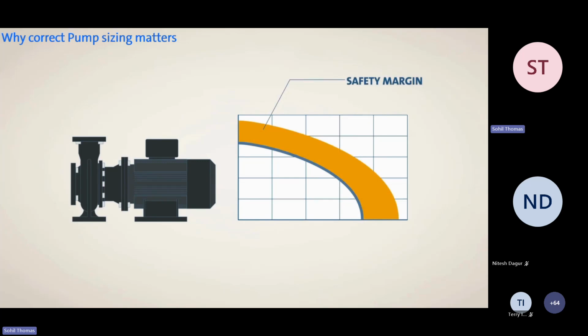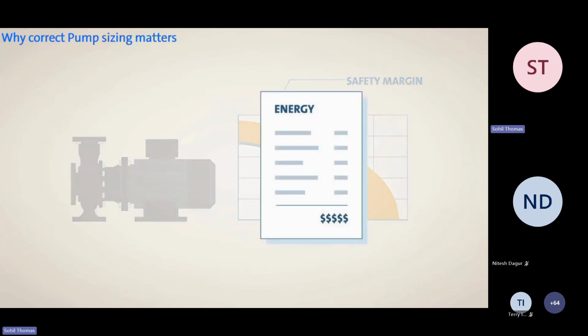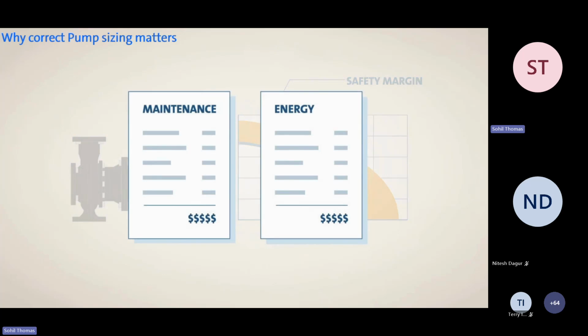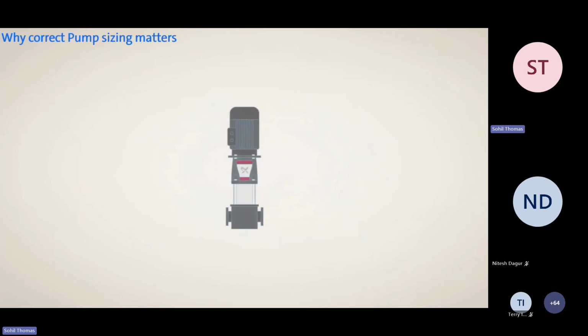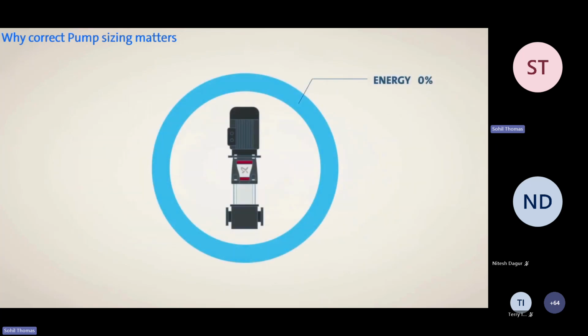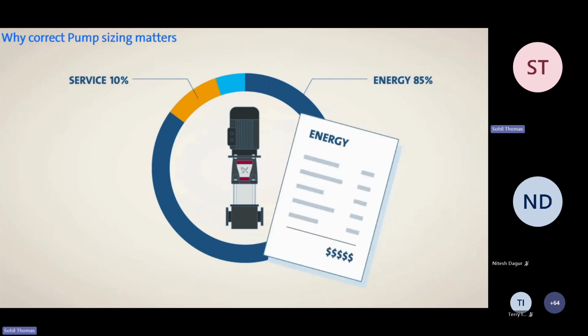However, if a pump is wrongly sized, it will add to system costs, both in terms of energy and maintenance, which brings us to the next point. Over the course of your pump's life, energy costs account for a massive 85% of the total costs, and service and maintenance costs account for 10%. So while a wrongly sized pump may provide a safety margin, it also means that the pump won't perform optimally, and that will have a massive impact on your energy bills.